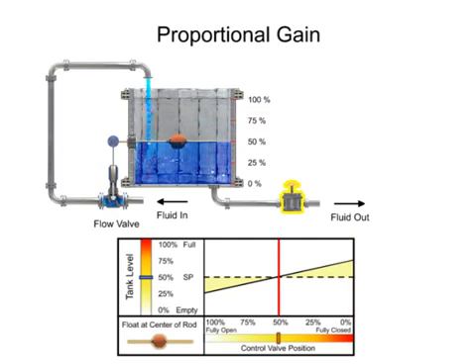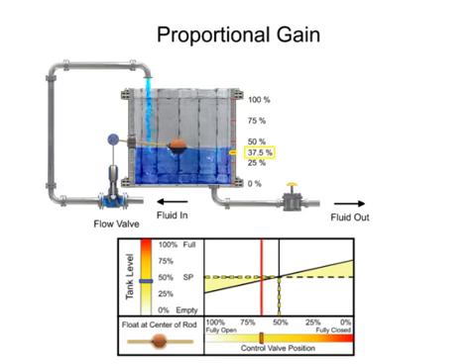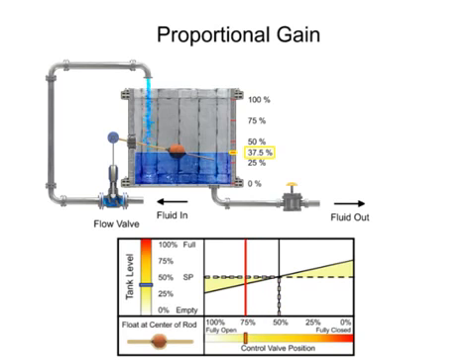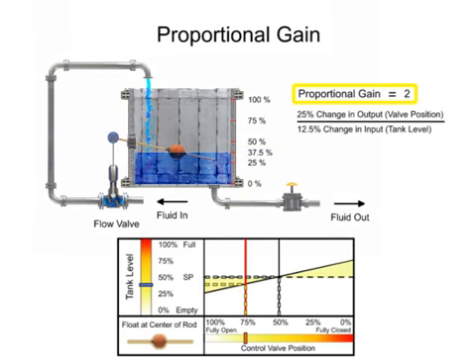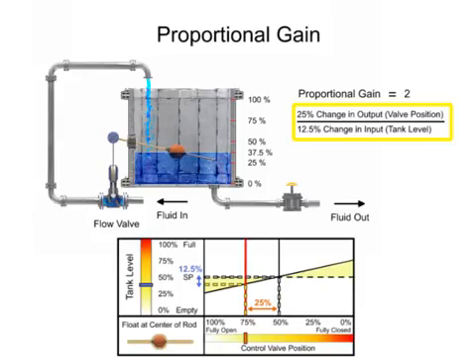Opening the drain valve increases the load demand, which causes the tank level to drop by 12.5%, or 37.5% full. The float drops and the valve opens 25%, which allows more fluid flow to enter the tank. A gain of 2 is demonstrated in this mechanism, since the 12.5% change of tank level resulted in a 25% change of valve position.